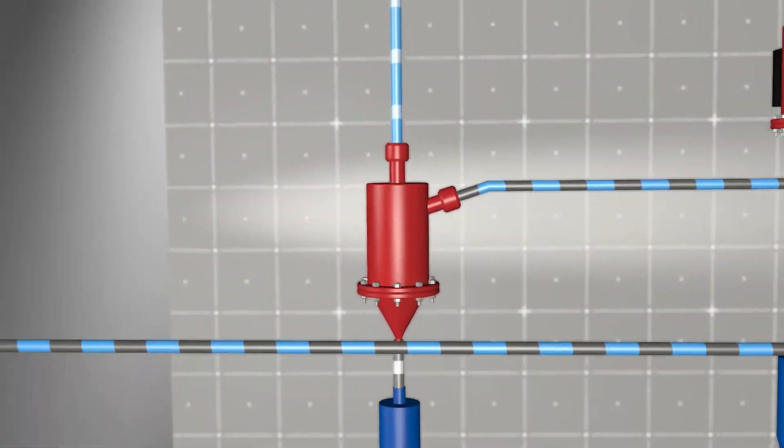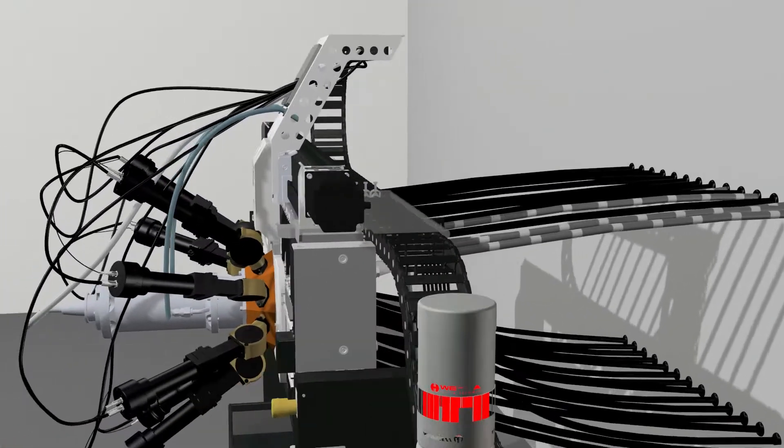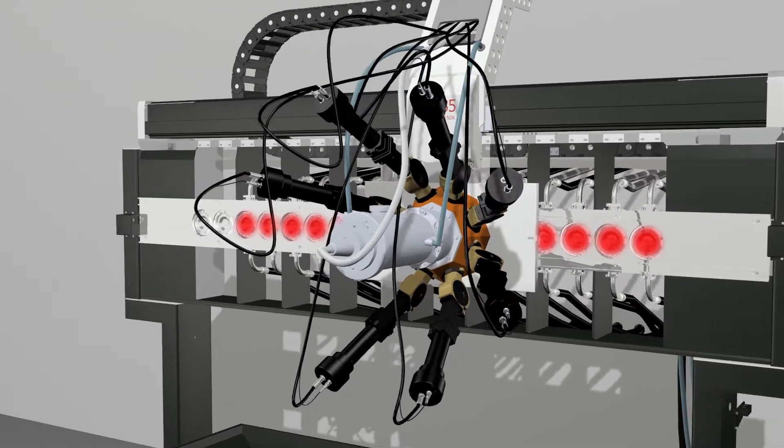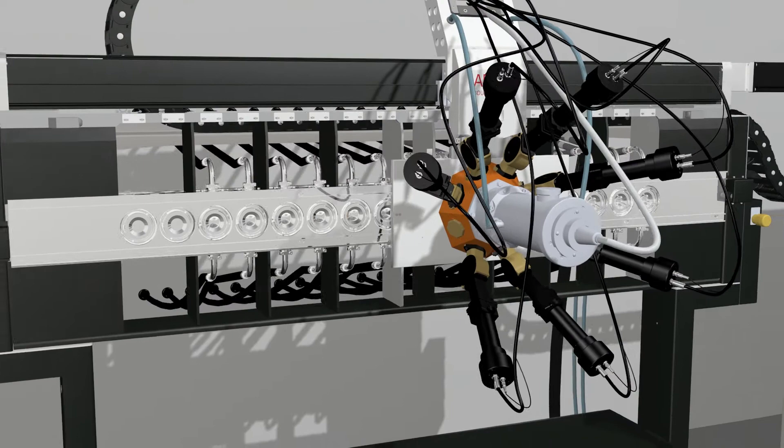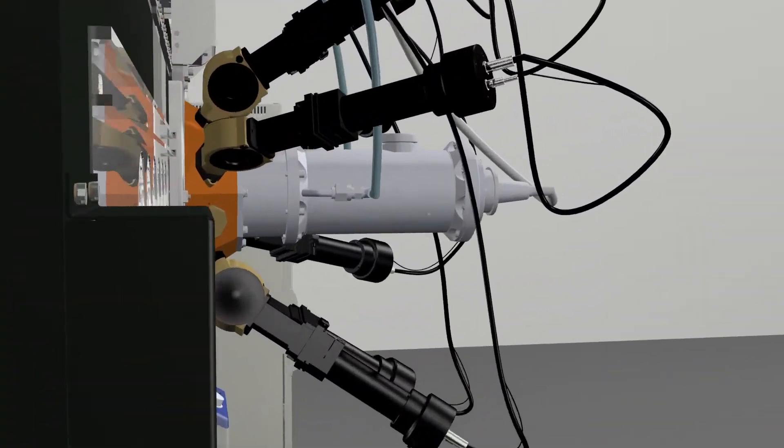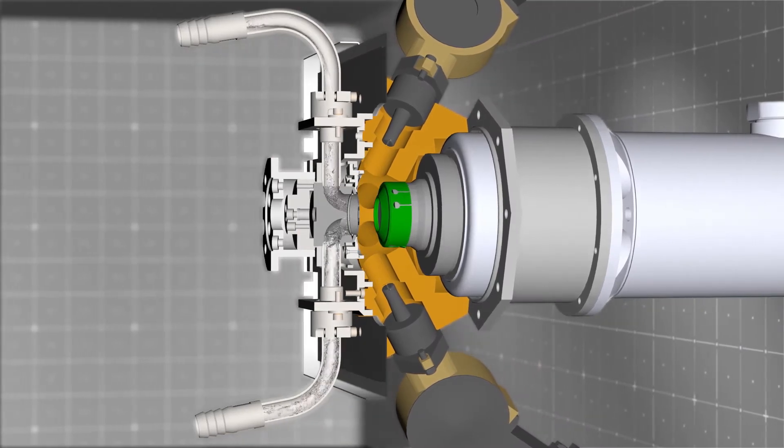The AR-35 analyzer allows consecutive analyzing of up to 15 streams. Every type of measuring product is analyzed in a separate measuring cell. This guarantees the exclusion of any measurement errors related to cross-contamination with other products that have different compositions. The analyzer is delivered with unique software.